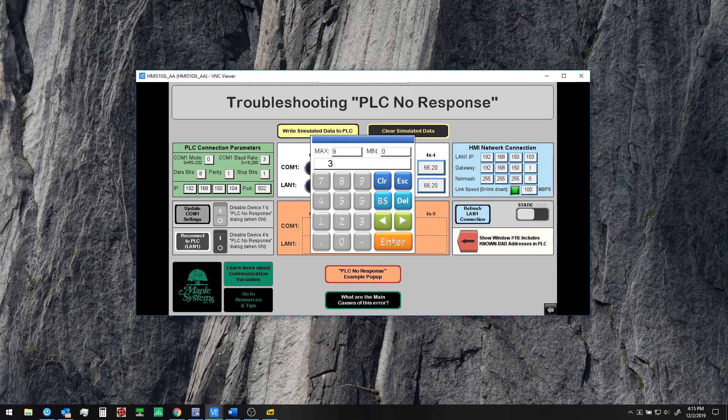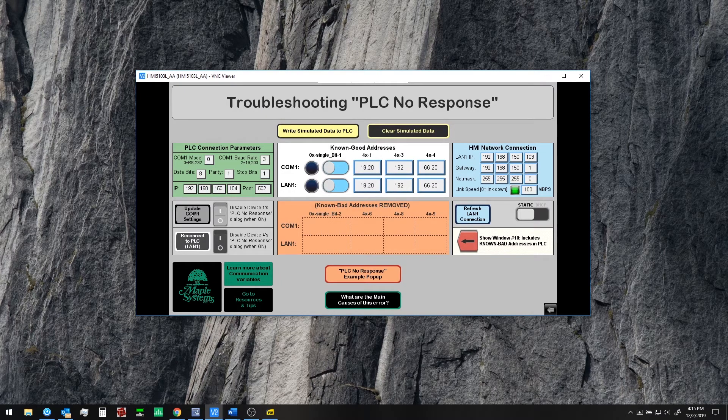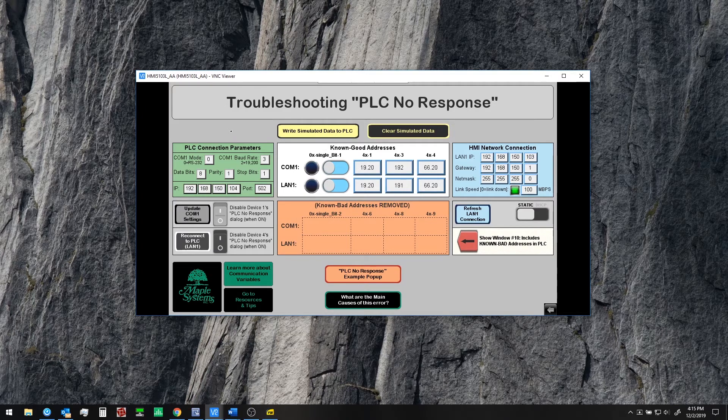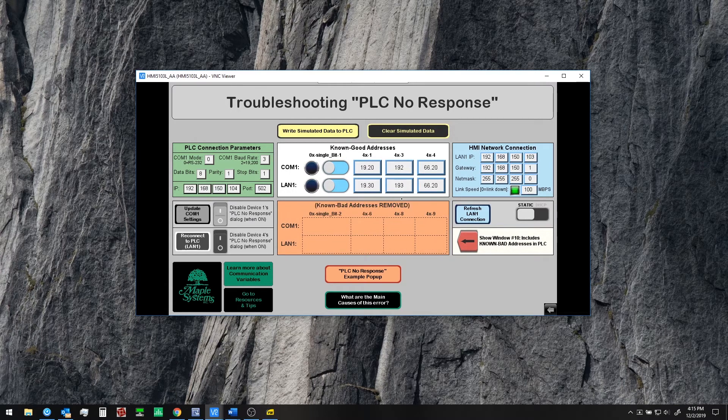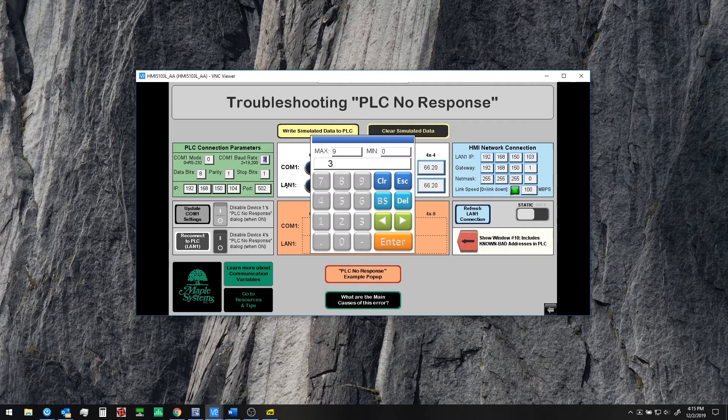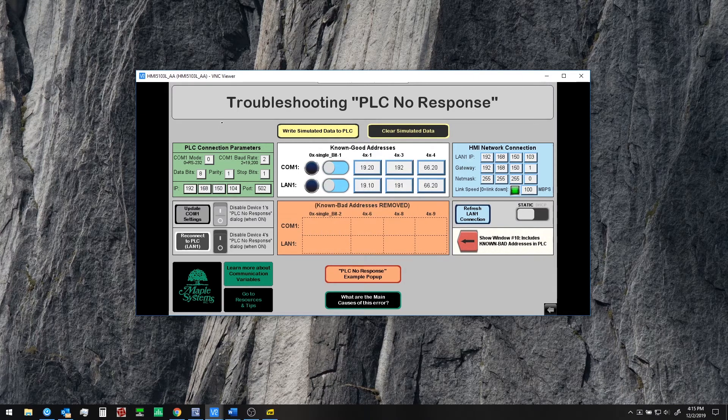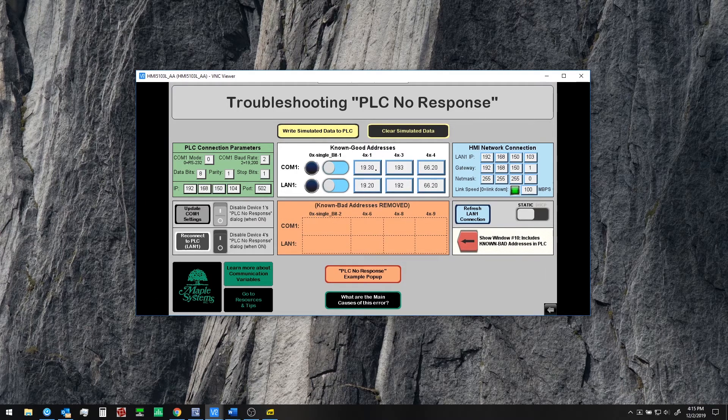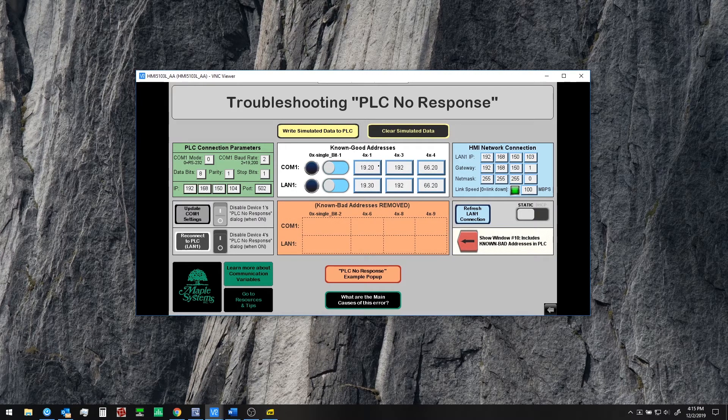If we change the baud rate to a different value and then update the COM1 settings. After a moment we should get a PLC no response. There we go. And if we go ahead and correct this. And update the settings again. We can now see these are both moving in unison and we're reading all the data from the PLC again.